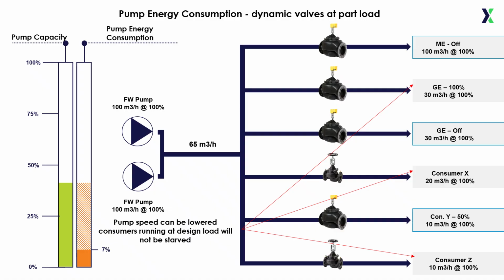With dynamic valves, the pumps can freely, by means of a variable frequency drive, be adjusted to match this reduced flow. Unlike static systems, where reducing pump speed risks starving consumers, dynamic valves ensure that all units, even those running at design load, continue to receive the correct amount of cooling water.